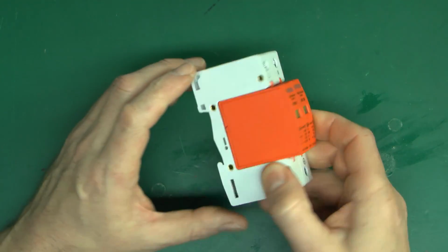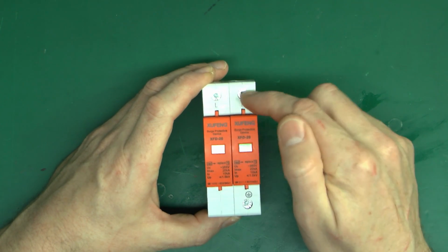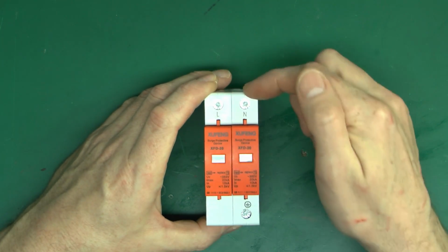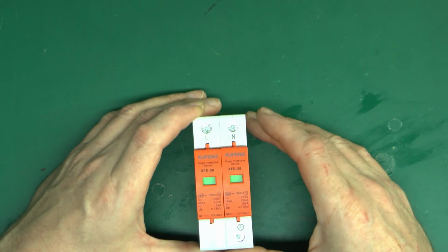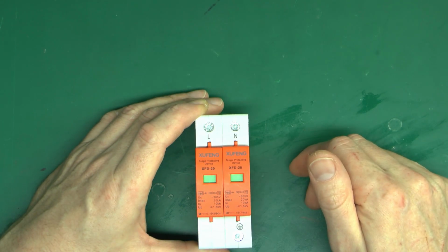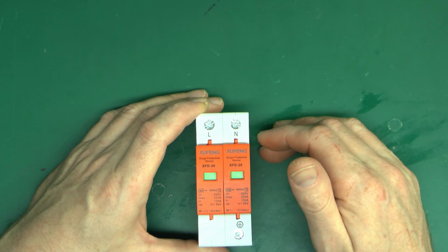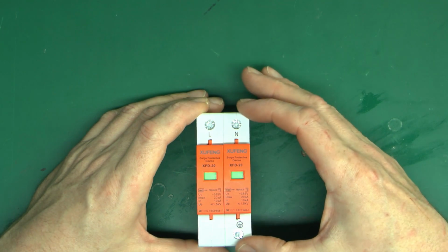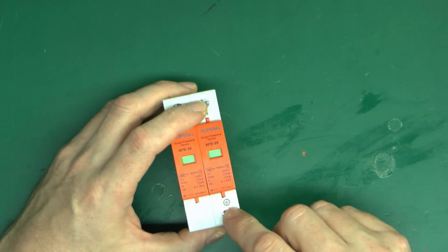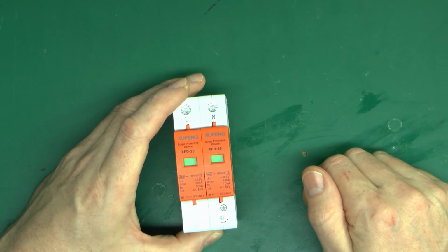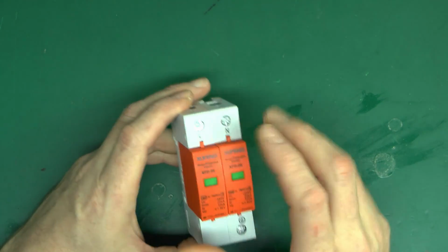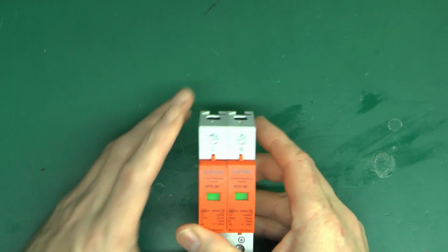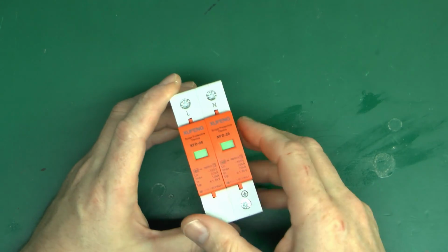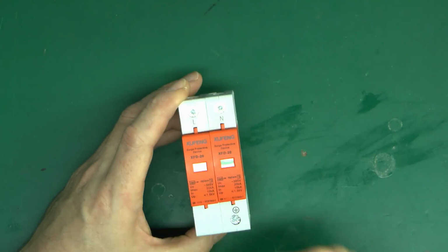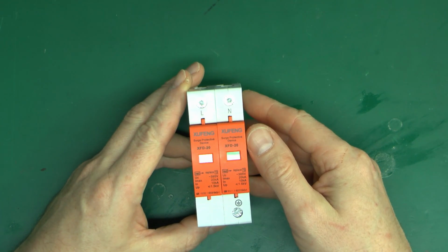So if it's in the consumer unit, not a problem, but do be aware of the fact that the neutral ideally is as short as possible. Don't sort of take it up and underneath and round the back in a nice tidy way, because obviously you can get to that 25 centimetres or so extremely quickly. Bearing in mind it's two added together, so if you've got 25 centimetres here and here, then that's two obviously adding up to 50. So keep the wires as short as possible, or do it in a separate enclosure and fit it on with the wires coming in and going out of the same piece of equipment.